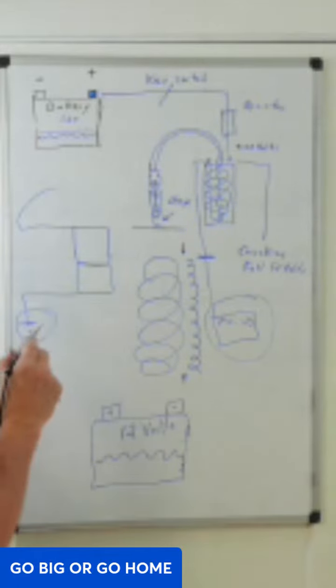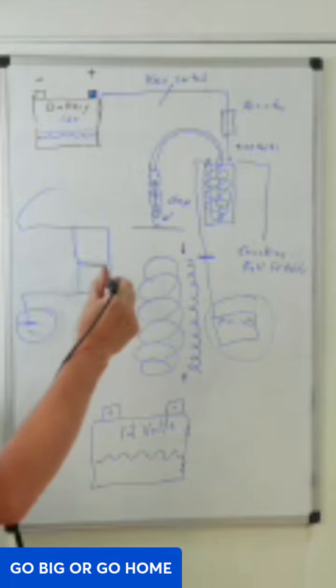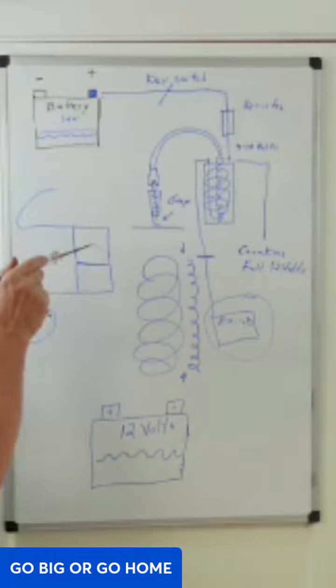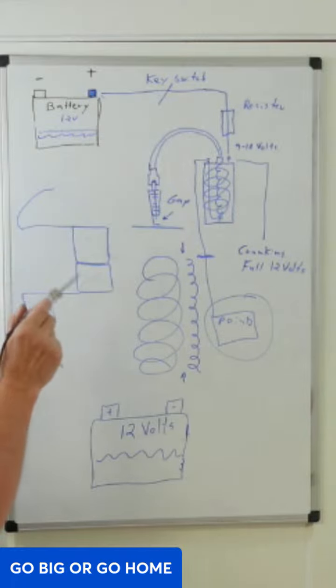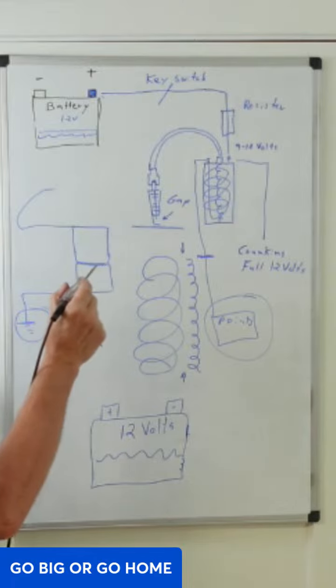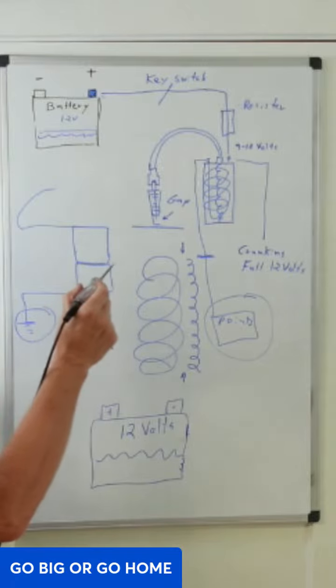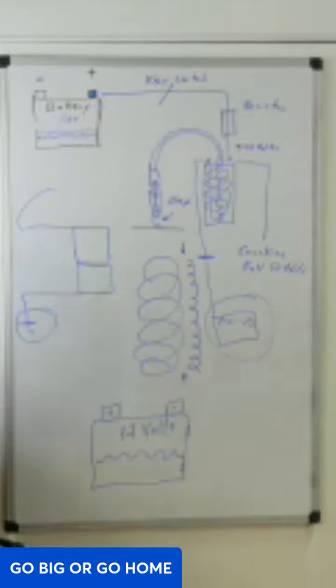What I found was when I came to the ground, I had ground here, the light lit. I had ground here, the light lit. When I moved over to the other set of contacts, I had no light. So what did that tell me? It told me either the points were open or worn out, or they had debris there. What I found out was they were just dirty.